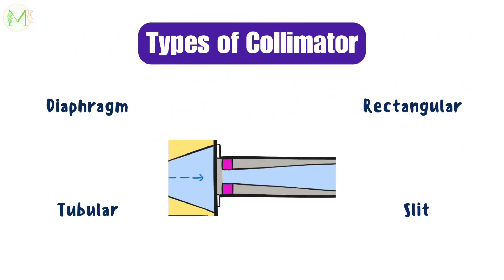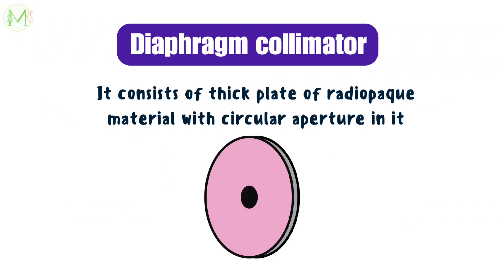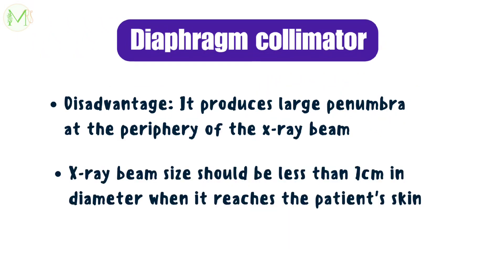The types of collimators are diaphragm, tubular, rectangular, and slit type. The diaphragm type of collimator consists of a thick plate of radiopaque material with a circular aperture in it. The size and shape of the aperture or hole determine the size and shape of the X-ray beam.